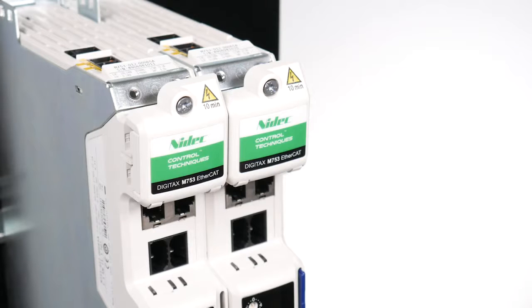The Digitax HD terminal and enclosure design enables the DC bus, ground connection, 24V supply, and communication ports of a number of drives to be connected together using premade bus bars and links to significantly reduce installation time and cost. Suitable bus bars and links for multi-axis paralleling are included in the multi-axis kits available as part of the Digitax HD installation and system accessories.